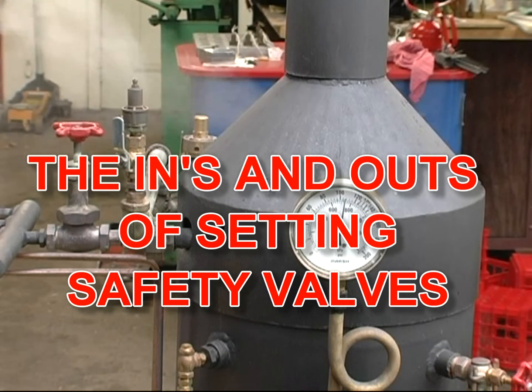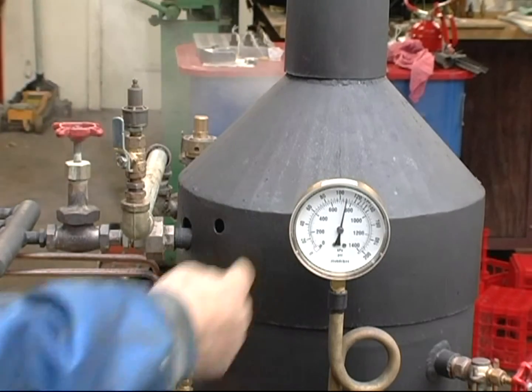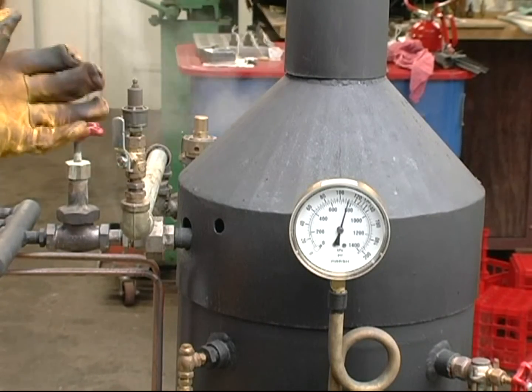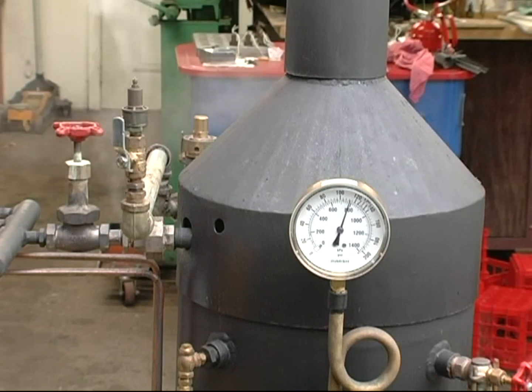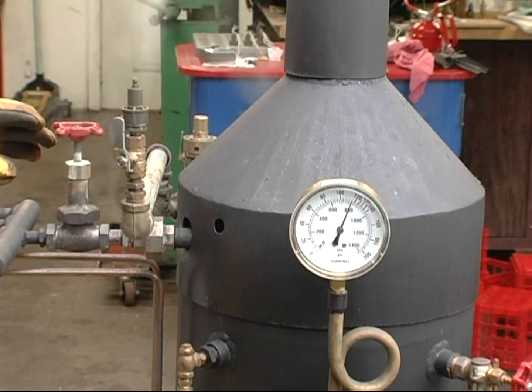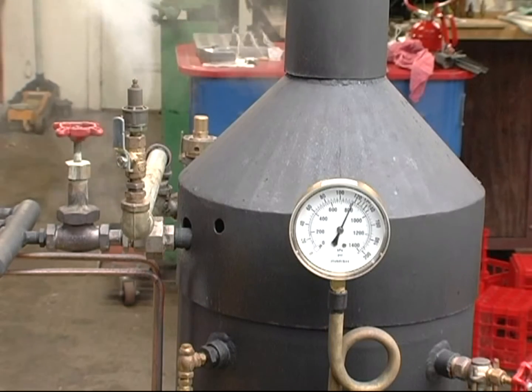We're here today testing the last couple of safety valves. I wanted to bring it up close so you can see the gauge and the safety we're testing. I put it on a ball valve because you have to be able to shut it off in order to test it — it's a little bit dangerous if the thing pops in your face when you're looking down inside. This valve goes off at about 120 and reseats at about 8 pounds under, which is a little more than I like, but sometimes you can't get it perfect. It varies with the volume of steam, but the main thing is the pop-off.